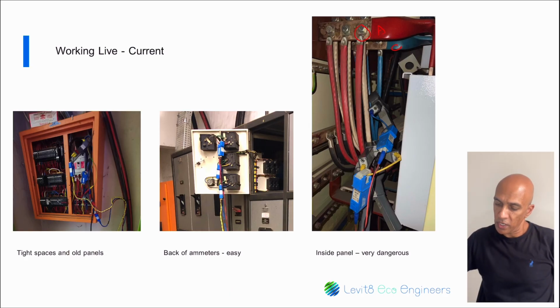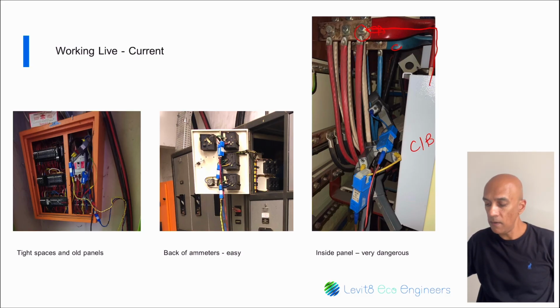Have a look at this connection here. We have connections that are right at the back of the circuit breaker. This is the circuit breaker, and we are looking at the panel from the side. And these bus bars come up this way and then out this way. Now, connecting onto these cables could be very difficult and challenging. So you need to make sure that you have your PPE on and try to find a location to connect onto the bus bars where you are not close to any bus bars or live parts. It's a very delicate operation, and you have to be extremely careful.